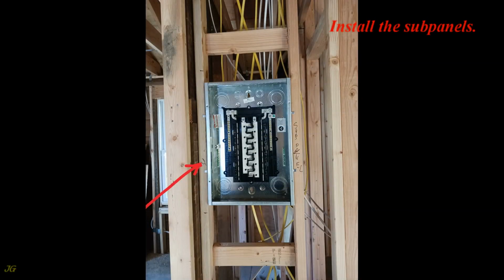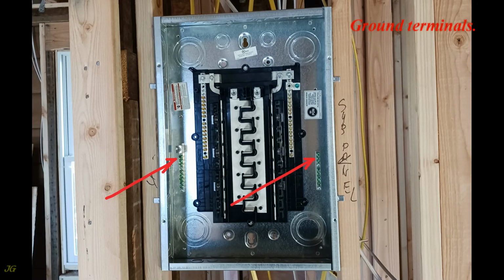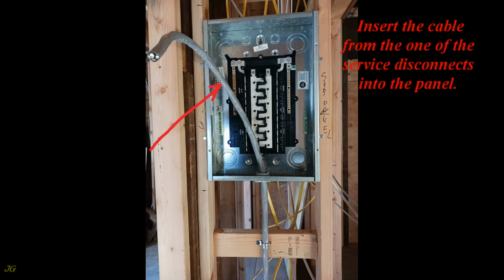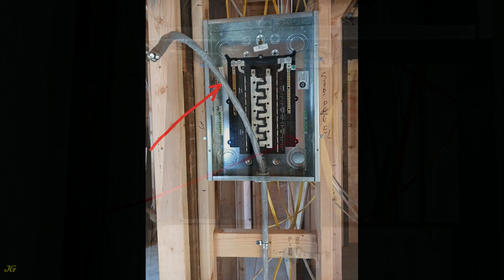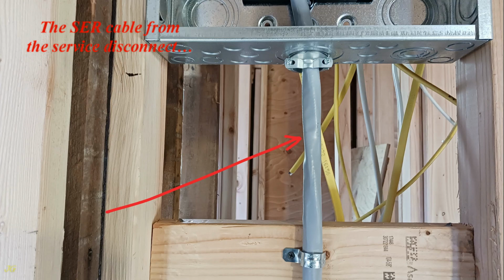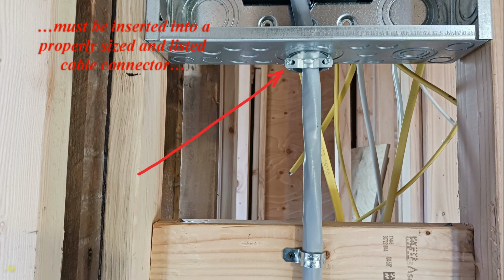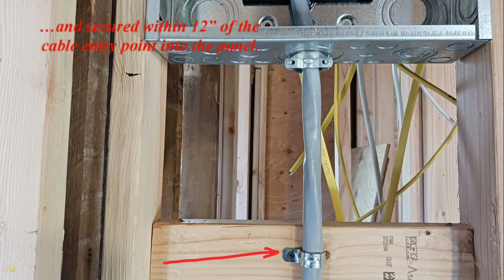Install the subpanels. Ground terminals. Neutral terminals. Hot terminals. Bonding screw for neutral bar. Insert the cable from one of the service disconnects into the panel. The SER cable from the service disconnect must be inserted into a properly sized and listed cable connector and secured within 12 inches of the cable entry point into the panel.